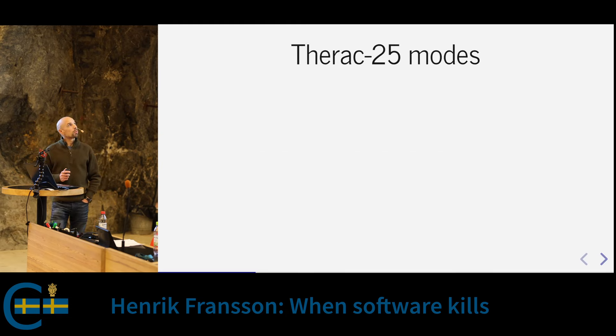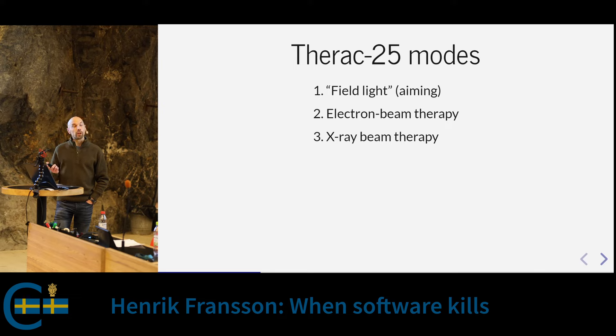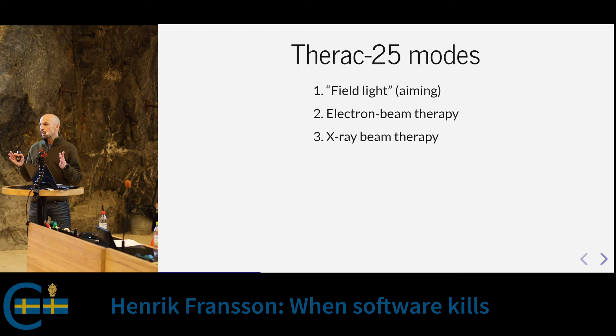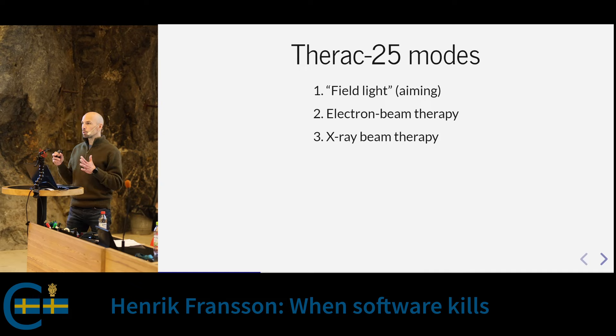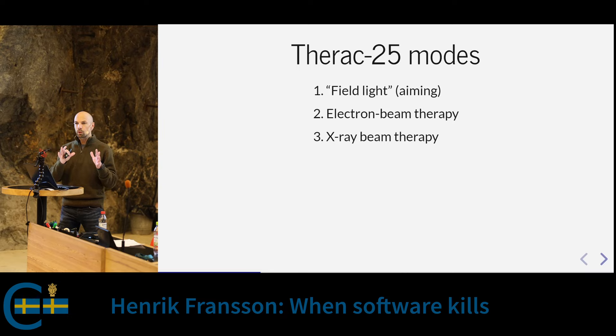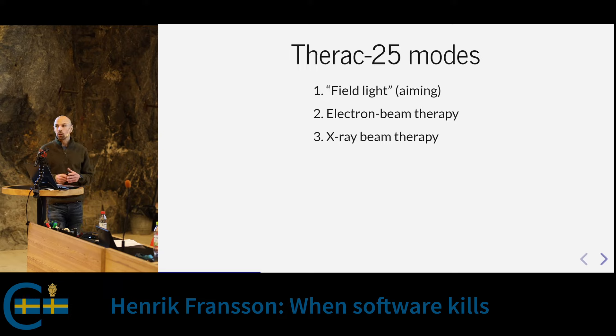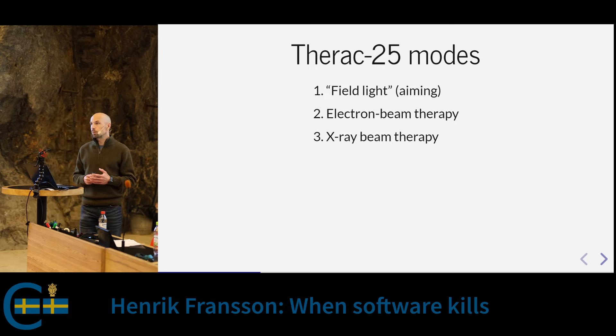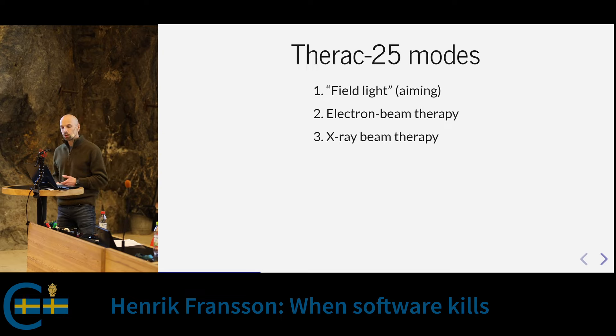The machine had three modes of operation. The first, called field light, was used when the operator was aiming the machine at the patient — a regular light bulb shining a dot onto the target, with no radiation. The other two modes were the two different therapy types: electron beam and X-ray beam, used depending on what kind of tumor you wanted to treat.